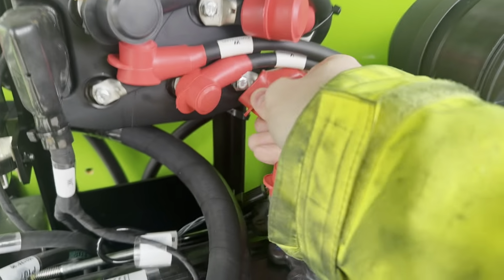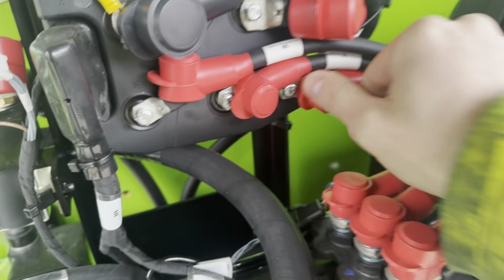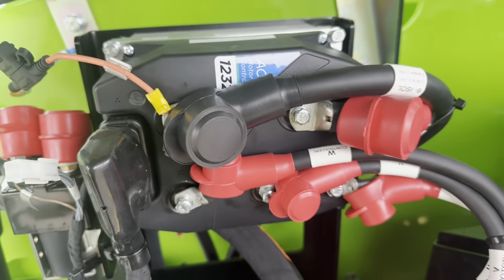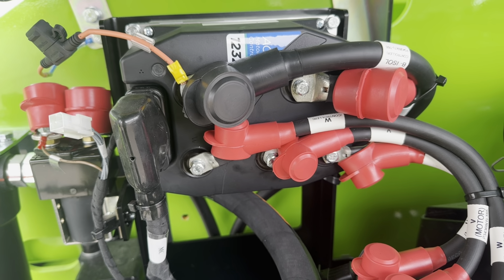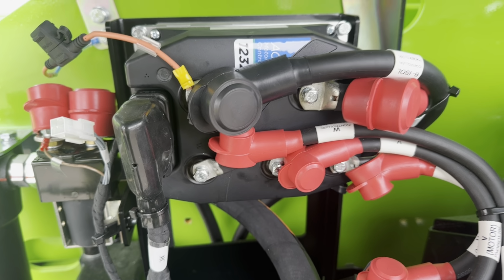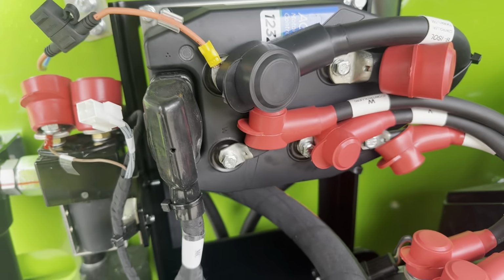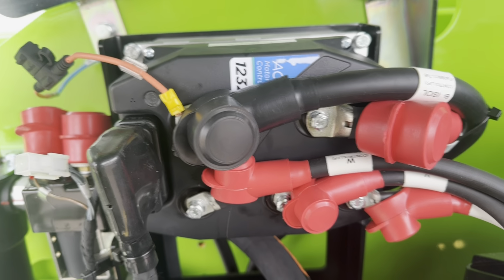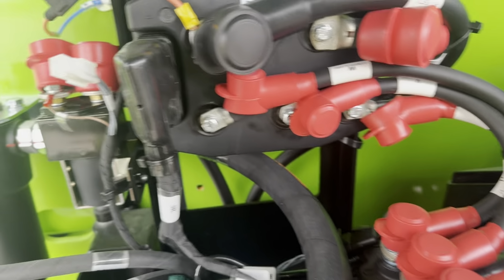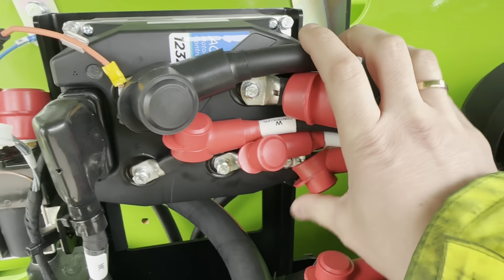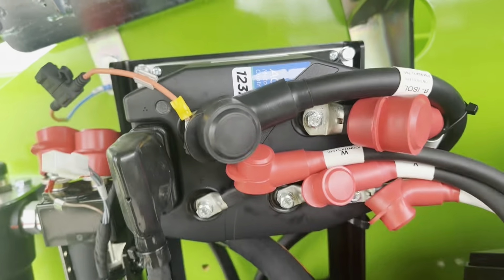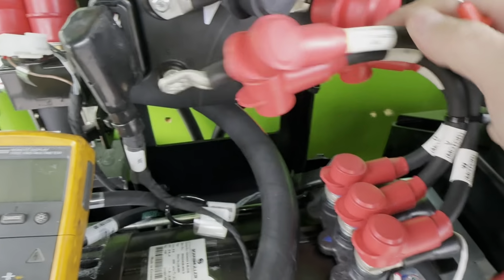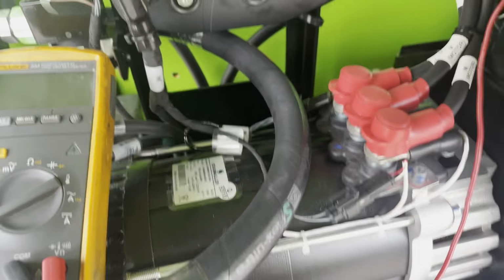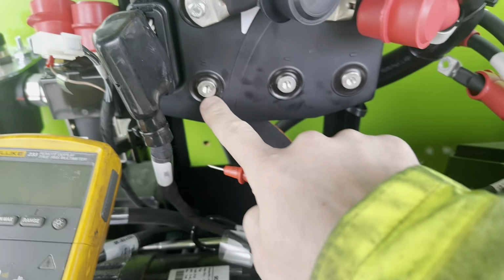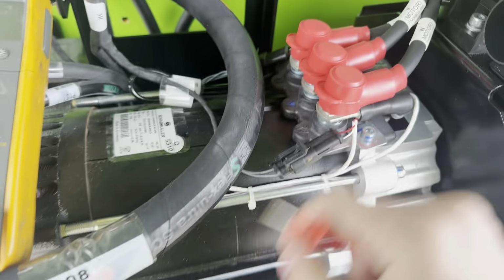The first thing, I will disconnect all the phases from the controller, so then we can do some resistance checks, and I will show you how to test the controller if there is a phase fault. So you can be sure if you have the error code, because I know that sometimes you may have the error code, but you're not 100% sure if that is the problem. But we will look into it, and I will show you how to be 100% sure that it is a problem with the controller. Okay, so all wires are disconnected from the controller. The motor is disconnected, so we can access the phases without any side effects from the motor itself.